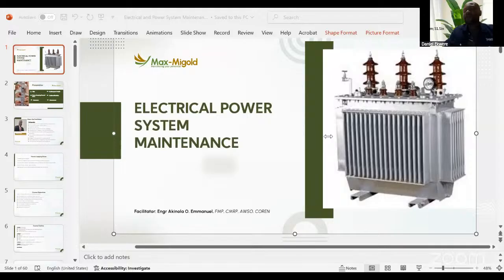Something happened in my office some time ago. We were running a genset of 350 kVA. The electricians were asked to let us know the load capacity we were running in the estate. They went around and captured the capacity of all the instruments we use, in kilowatts, and concluded that the whole load in the estate was about 400-something kilowatts. Because of that, they said we needed a 500 kVA generator, not realizing that not all these instruments work at the same time. So the company acquired a 500 kVA genset.